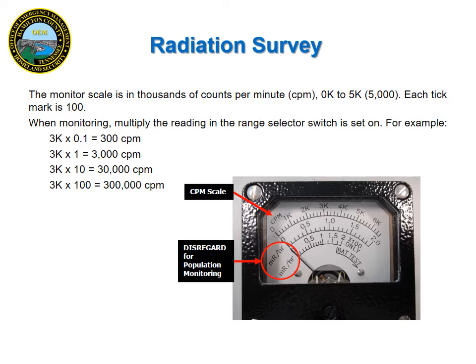So when monitoring, you will have to do some math depending on where the range selector switch is set. So take, for example, the needle is on 3K. If that's true, then if the switch is on times 0.1, then the actual reading is going to be 300 counts per minute. If the range selector switch is on times 1, the reading will be 3,000. For times 10, it's going to be 30,000, times 100, 300,000.